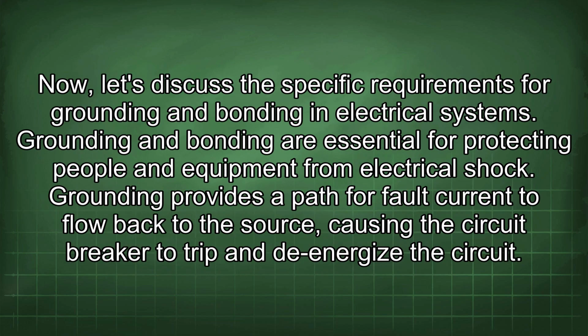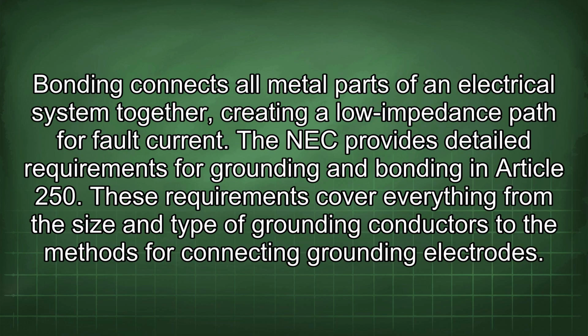Now let's discuss the specific requirements for grounding and bonding in electrical systems. Grounding and bonding are essential for protecting people and equipment from electrical shock. Grounding provides a path for fault current to flow back to the source, causing the circuit breaker to trip and de-energize the circuit. Bonding connects all metal parts of an electrical system together, creating a low impedance path for fault current. The NEC provides detailed requirements for grounding and bonding in Article 250.